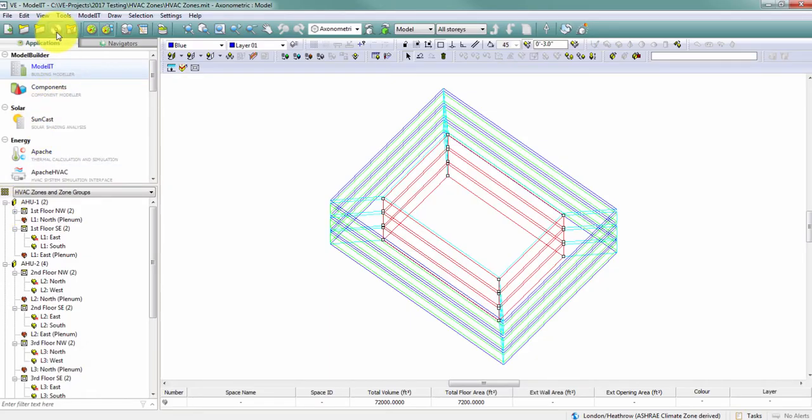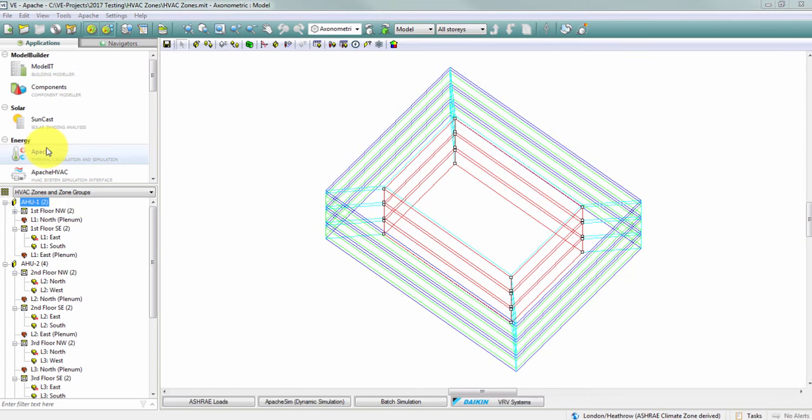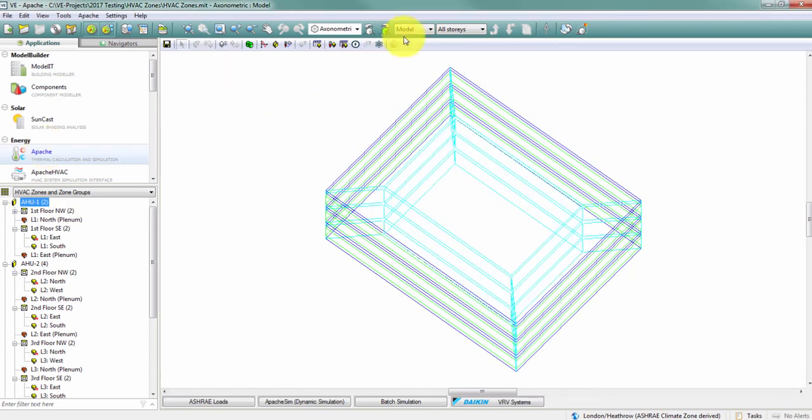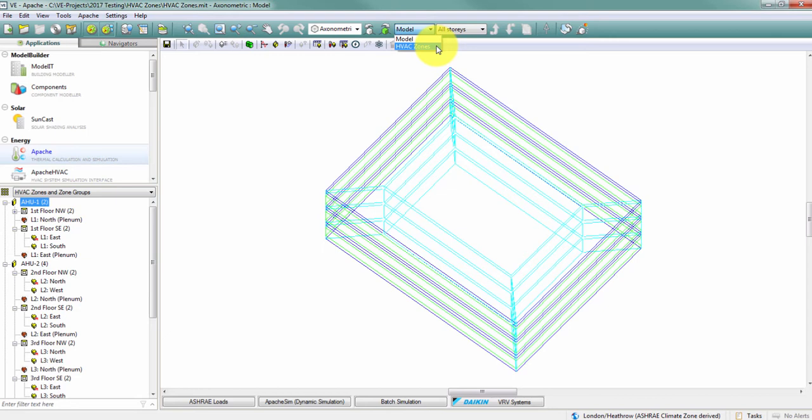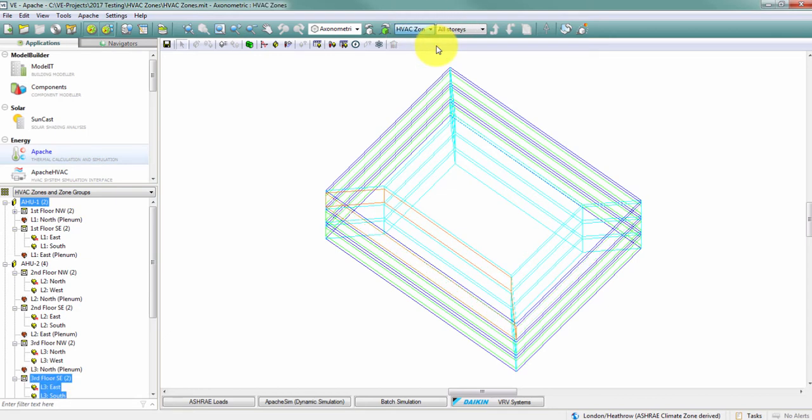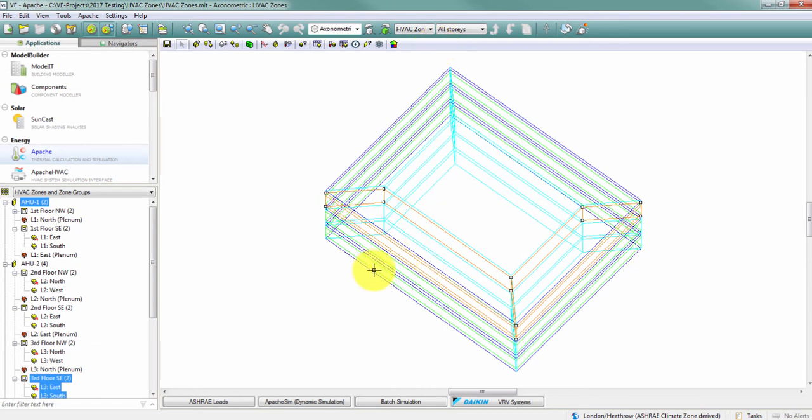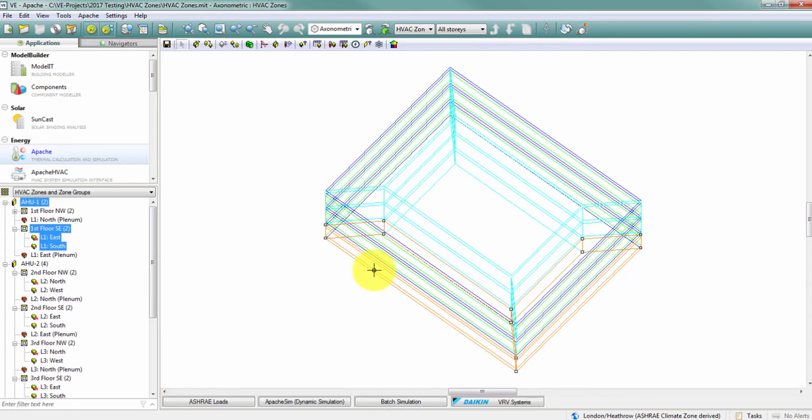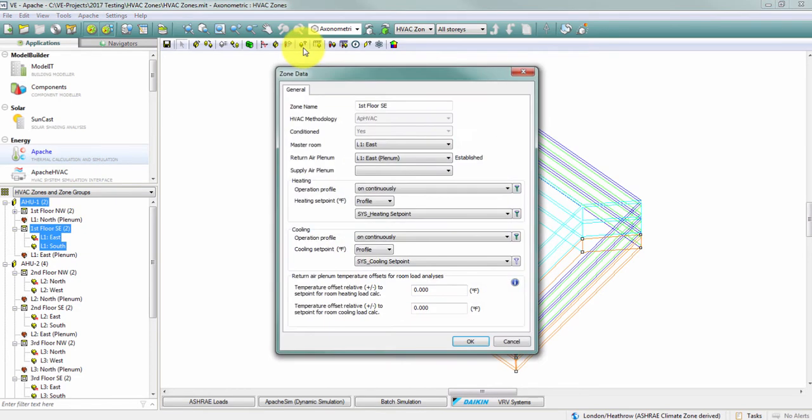If I save my model and I switch over to Apache, I now have an option to access an HVAC zones display mode. So by toggling the option up here in this pull down menu, I can switch into HVAC zones display mode, and now if I click a space on my model, I'm actually selecting the zone instead of the space. Likewise, the function of the query button has changed, so if I now query this zone, I get a zone data dialog as opposed to the space data dialog you're previously familiar with.